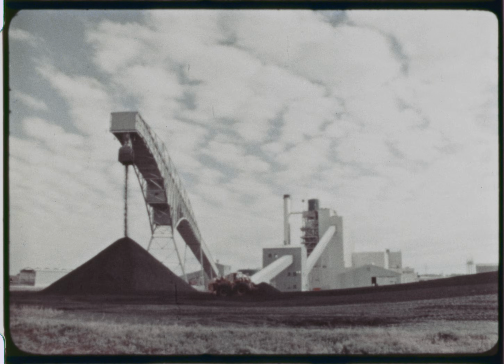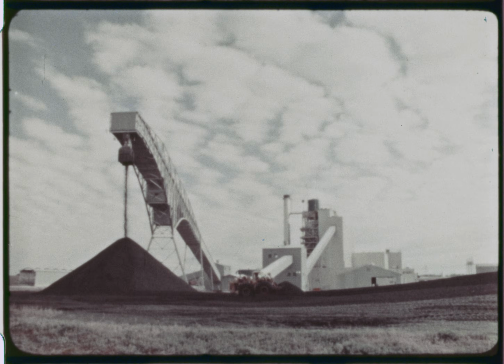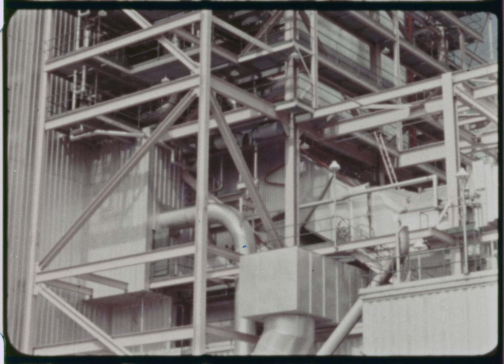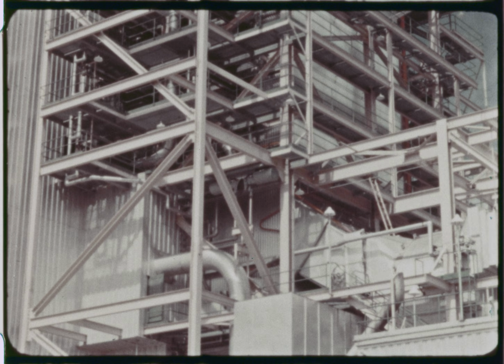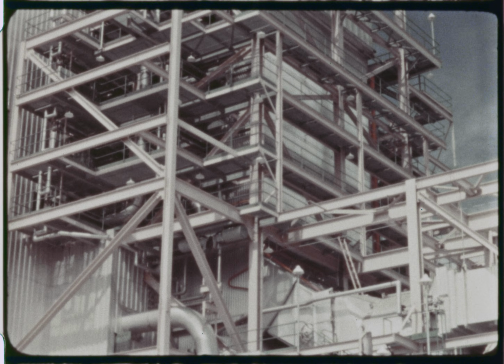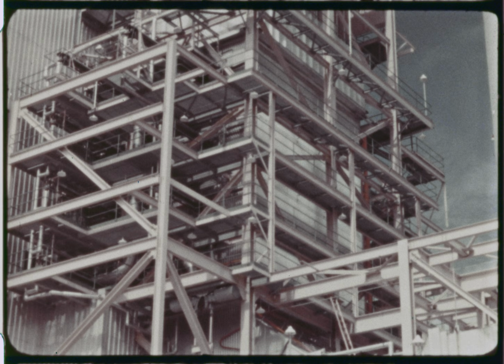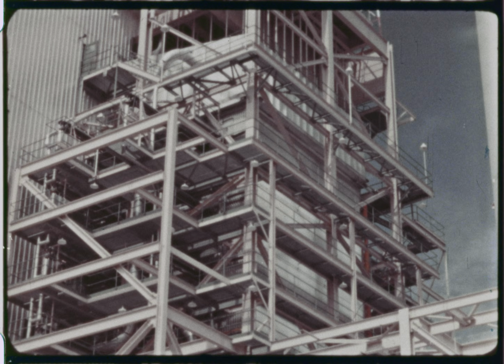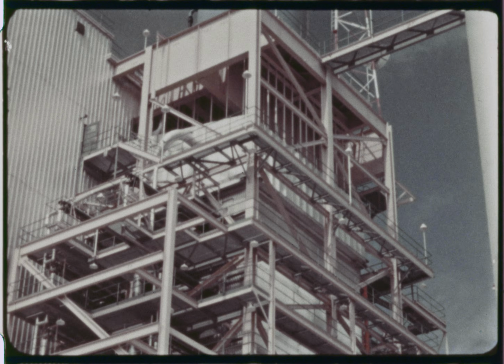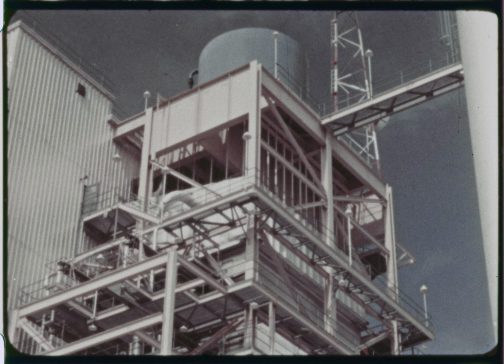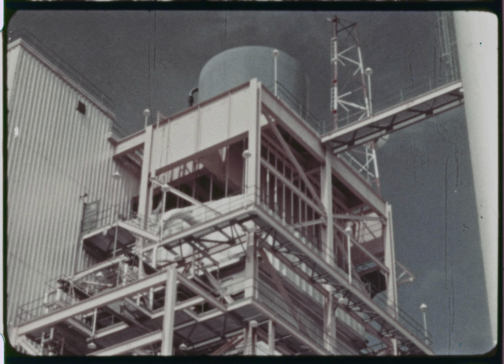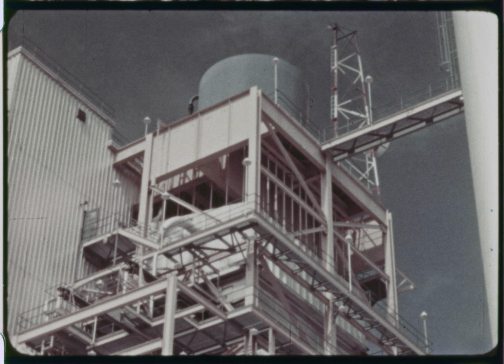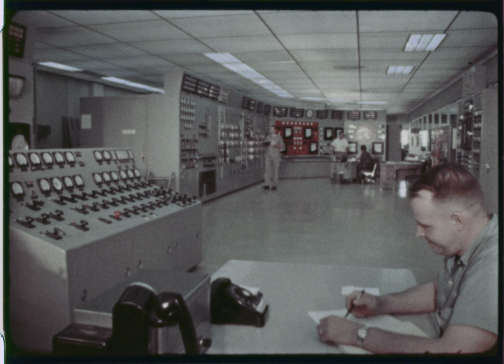The conventional boiler and auxiliaries with the turbine generator, now operated as part of the nuclear facility, were installed by Consumers to supply generating capacity needed in advance of the nuclear facility's completion date and during the period of reactor test operation. The conventional facility was designed to match the reactor steam conditions of 800 pounds per square inch of pressure and 825 degrees Fahrenheit temperature.